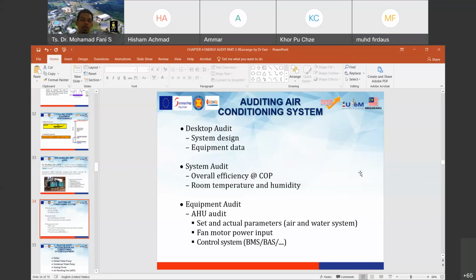For example, inside the room we measure the temperature and the value is lower, or much different from the set point. The engineer must do something, such as ask their technician whether the sensor is broken or something happened to the chiller system.